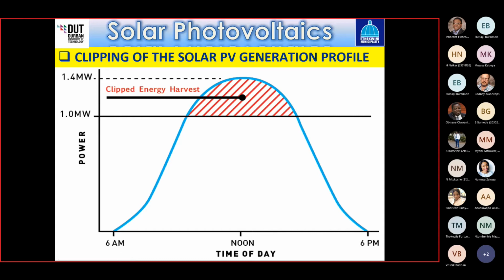So what happens if, as we said, we put in 1.4 megawatts of DC panels, and we've got 1 megawatt of AC inverters? Typically, and this will depend on the tilt angle, the orientation, and whether there's any shading or other aspects, on a really clear day, let's assume that the DC produced is 1.4 megawatts, but your inverter is only rated at 1 megawatt. So what happens is the inverter will basically clip off anything above a megawatt. You would get the area under the graph, which is basically the total kilowatt hours generated by the system. This typically would only happen in summer.